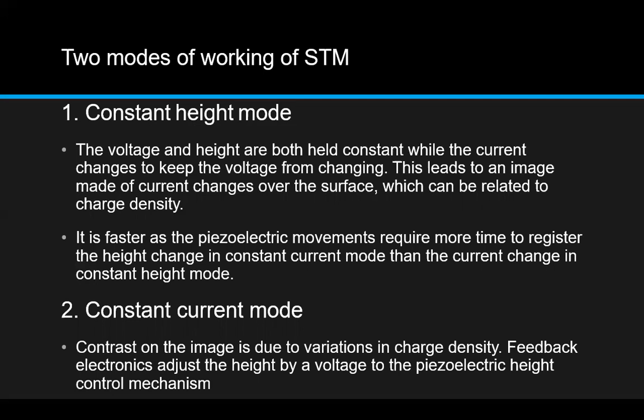The second one is the constant current mode. The contrast in the image is due to the variation in the tunneling current. The feedback electronics adjust the height by the voltage, and the piezoelectric height control mechanism.